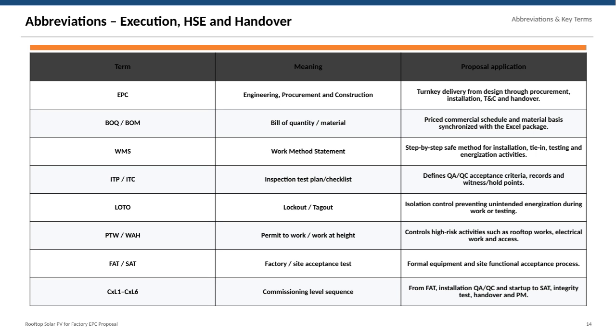Inspection and quality control are managed through ITP or ITC, meaning Inspection Test Plan or Checklist, which specifies acceptance criteria and records key checks. Safety is a priority, with LOTO lockout/tagout, ensuring isolation to prevent accidental energization during work.